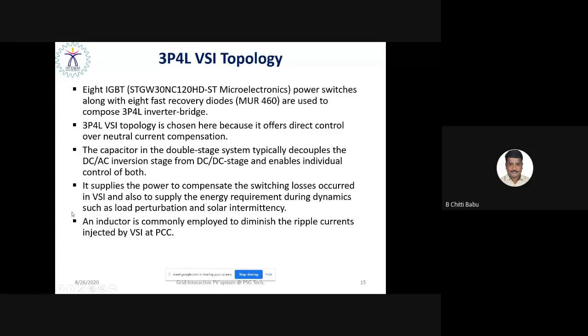Why? Whenever there are step changes, or whenever there is a variation in temperature and irradiation, obviously there must be changes in the DC link voltage as well. So it has to be maintained constant irrespective of source variation or load variation, right? So mostly we use either an ultra capacitor or a super capacitor, or an energy source like a battery in line with it. That has to be incorporated in the DC link, so that the DC link voltage remains constant irrespective of source fluctuation or load fluctuation. Please remember that. And the inductor is connected in the inverter so that it reduces the current ripple. That is very important, because the inductor reduces the ripple in the current wave, and no DC component must be injected at the PCC. That I will tell you.